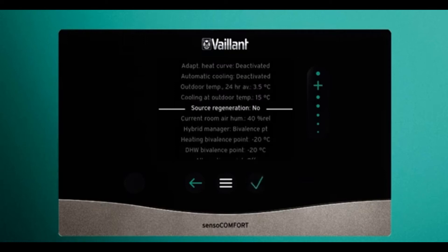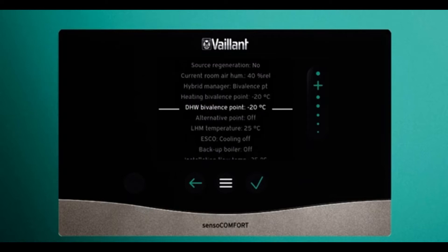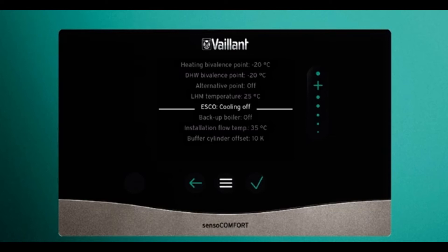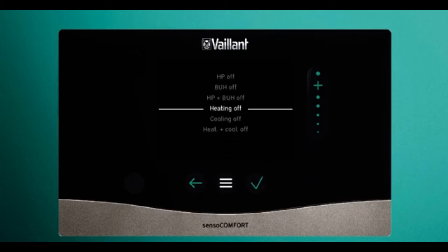Keep going down. Bivalence points should be set at minus 20 unless you are using your system as a bivalent, meaning you have backup heaters built into the system that come on at different temperatures. ESCO should be set as cooling off unless you have third-party thermostats connected and wired into the EVU connection, in which case it should be set to heating off.